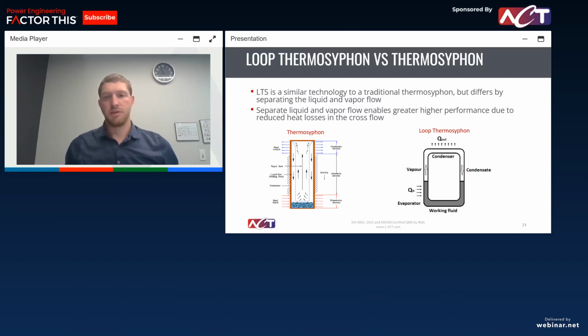So that leads into loop thermosyphon. It's a similar technology to that traditional thermosyphon, but the main difference is that we're separating our liquid and our vapor flow. So in that normal thermosyphon, as you can see on the left, your vapor and your liquid are in cross flow, going right past each other as they're moving up and down the thermosyphon. In a loop thermosyphon, you actually are going to have a separate vapor line and a separate liquid line. So your liquid is going to travel from your condenser down to your evaporator in one section, and your vapor is going to travel back up in a separate line. So that elimination of the cross flow eliminates some of those heat losses, and you're going to see much higher performance with the loop thermosyphon.